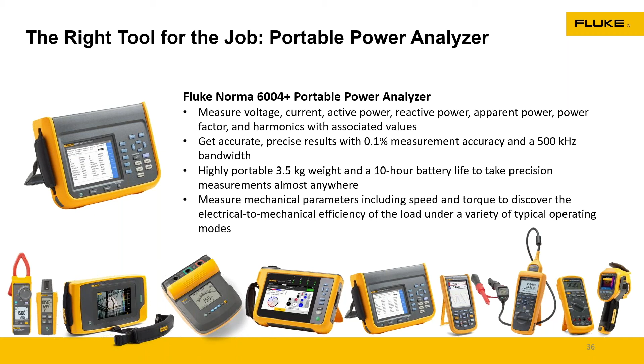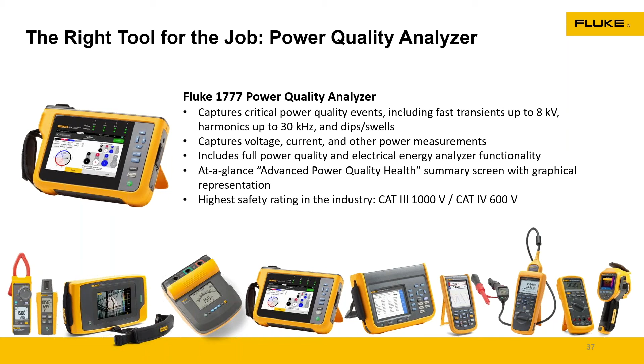Now the 1777 is an AC only unit, great, with a touch screen. This helps us on the AC side of the inverter. As I mentioned with that company in Georgia, where everything was working fine with the system, it was actually the utility side causing the error. Having this type of unit validates that information so you can report it back to the utility to get it resolved and get the system up and running again.